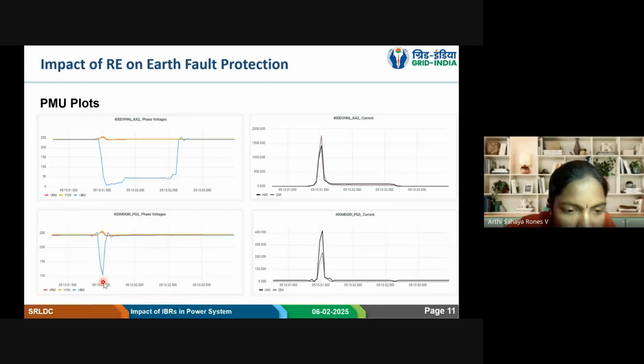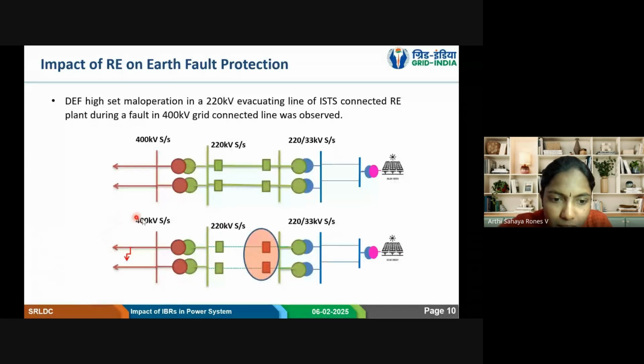Only a transient fault signature we are seeing from the PMU, indicating a dip in the B phase voltage. So the B phase pole of this particular line has opened and it has reclosed, and there is no persistent fault. Whenever the fault was there, during that time, we will be having negative and zero sequence current in the grid. So these are all grid side things. This end, what happened, I'm telling.